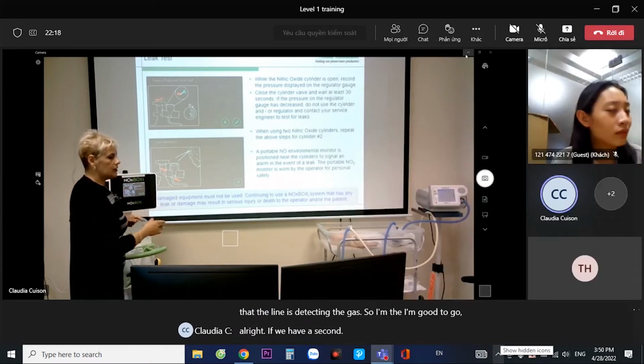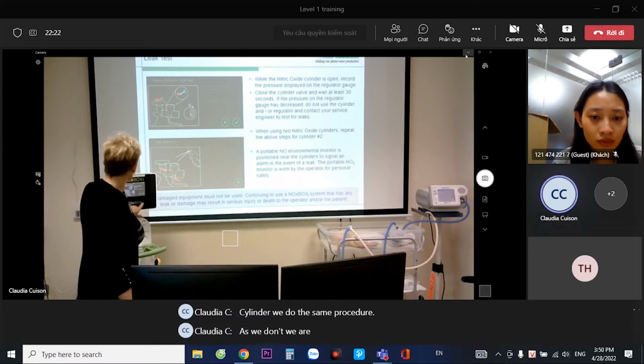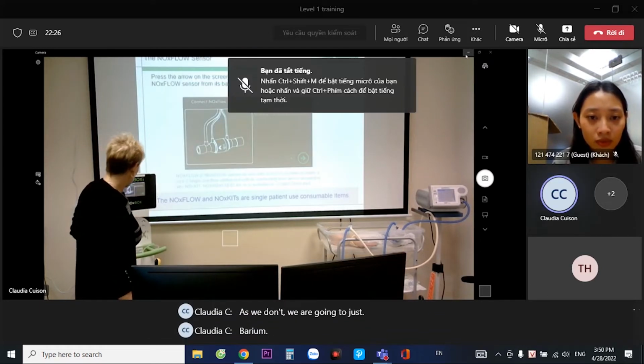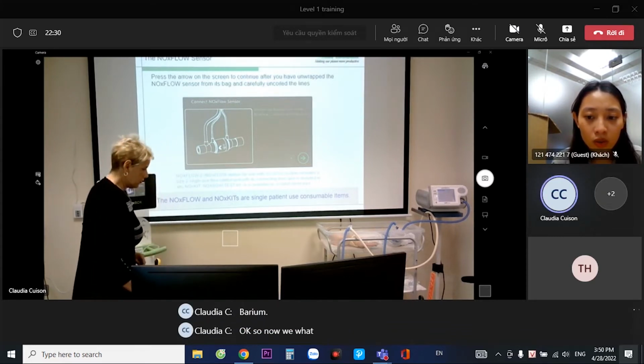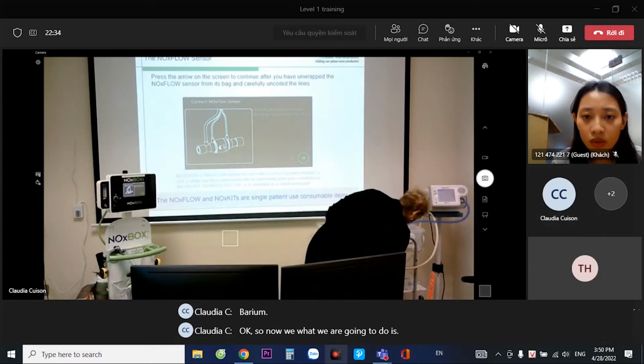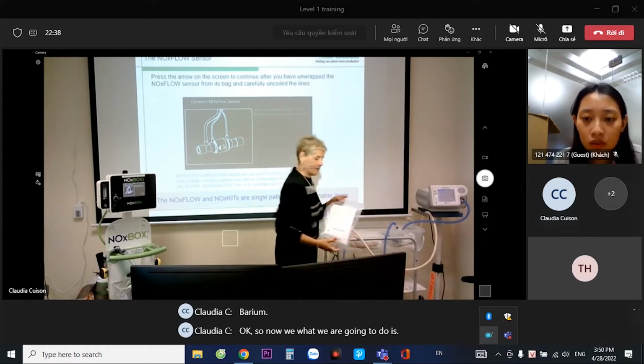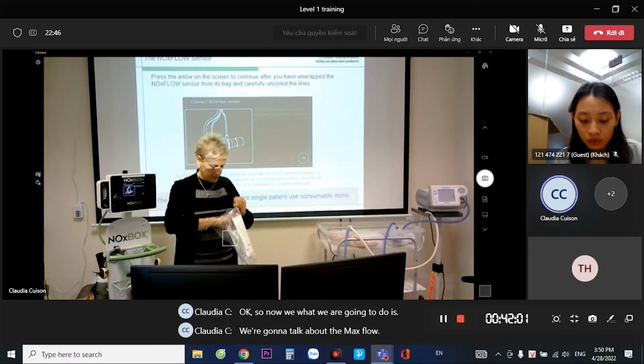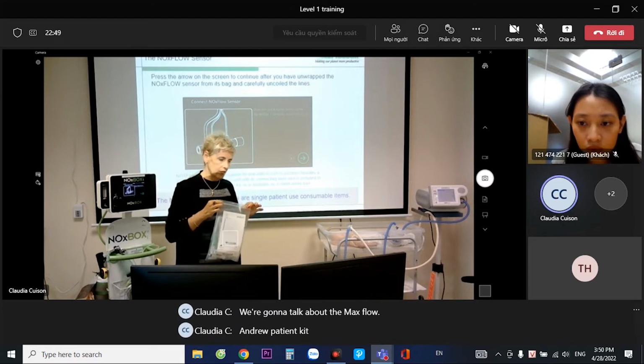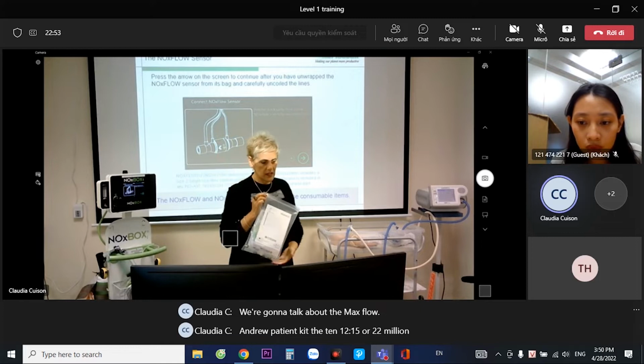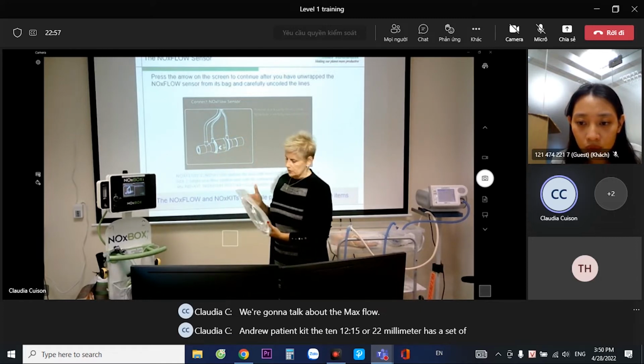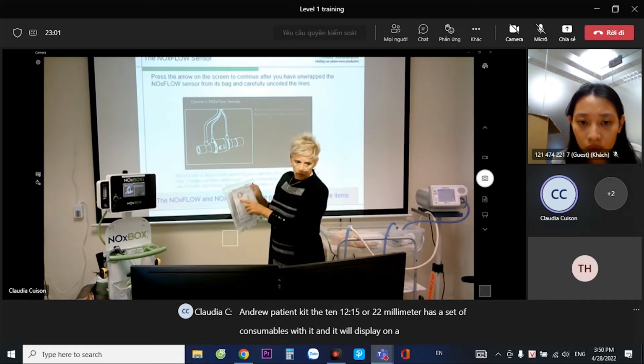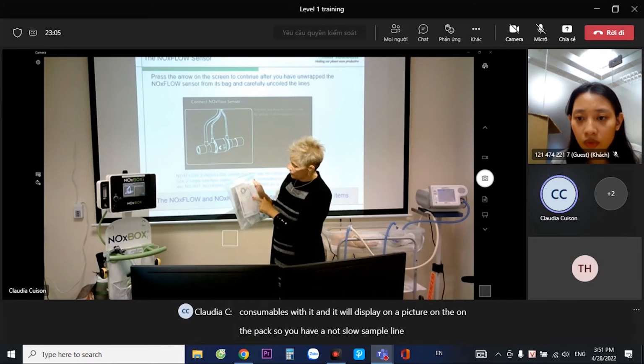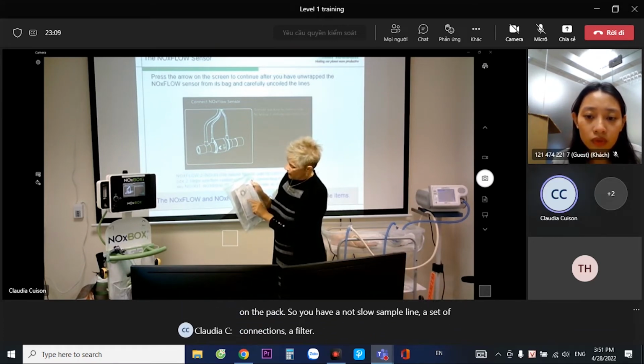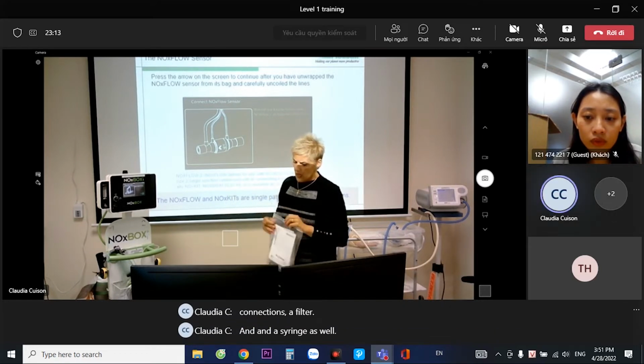All right. If we have a second cylinder, we do the same procedure. As we don't, we are going to just carry on. Okay, so now we're going to talk about the NOx flow. Every patient kit, the 10, 12, 15, or 22 millimeter, has a set of consumables with it, and it will display on a picture on the pack. So you have a NOx flow, sample line, a set of connections, a filter, and a syringe as well.